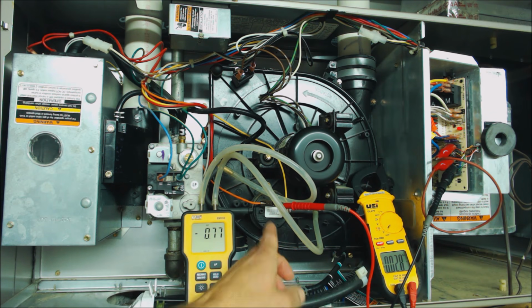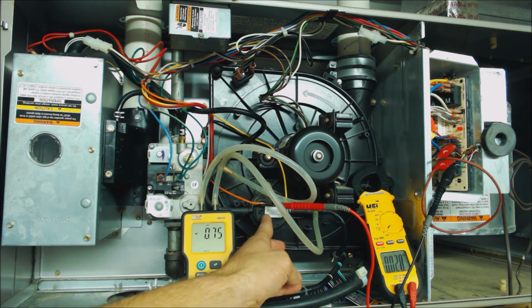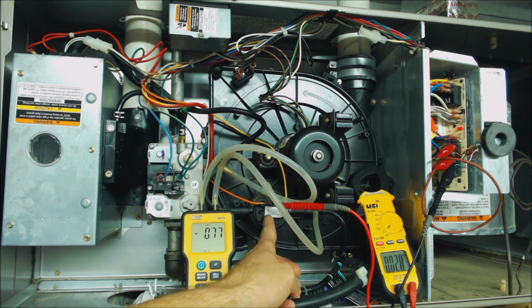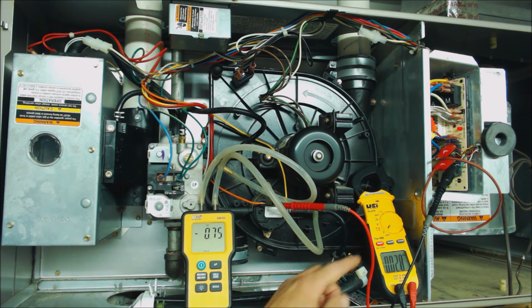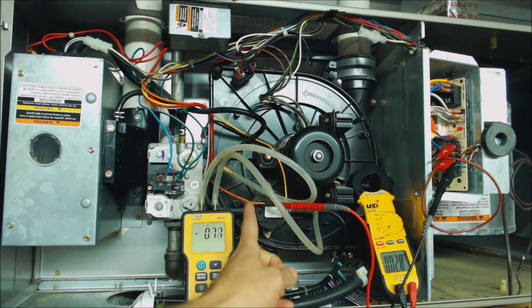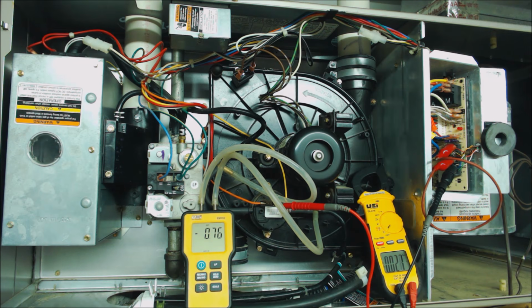-0.75. So when we look this model number up, sometimes the pressure switches will say the negative inch water column readings on them, but in this case it didn't, so we had to look the model number up. This one has to have -1.81 inch water column in order for the switch to close. Presently we still read 0.028. So that's not 28 volts, it says there, it's 0.028. So that means that we don't have any voltage to this side of the pressure switch.